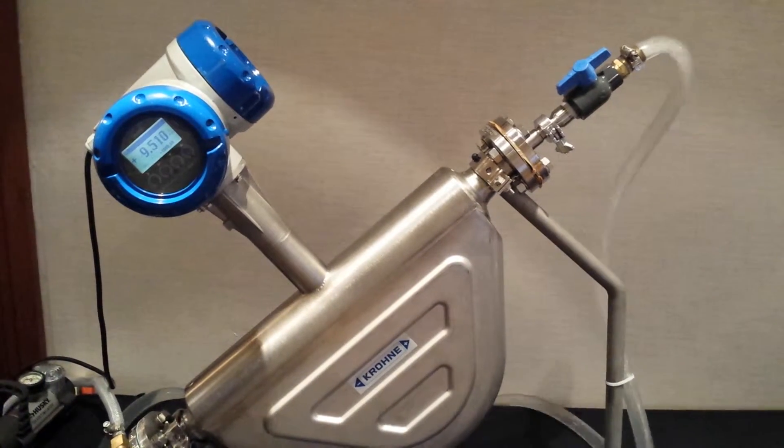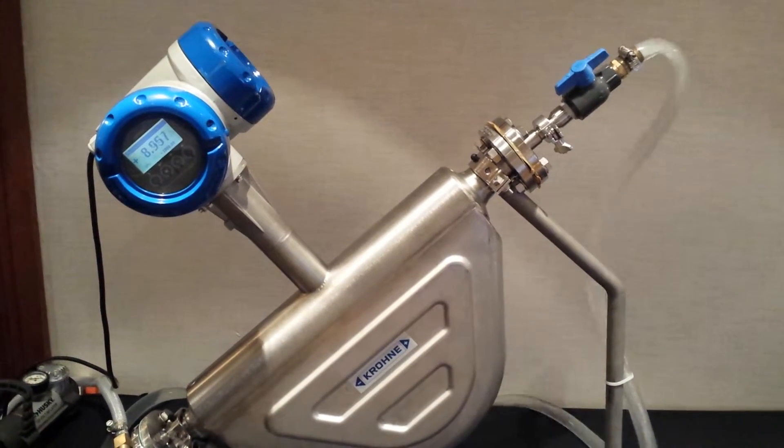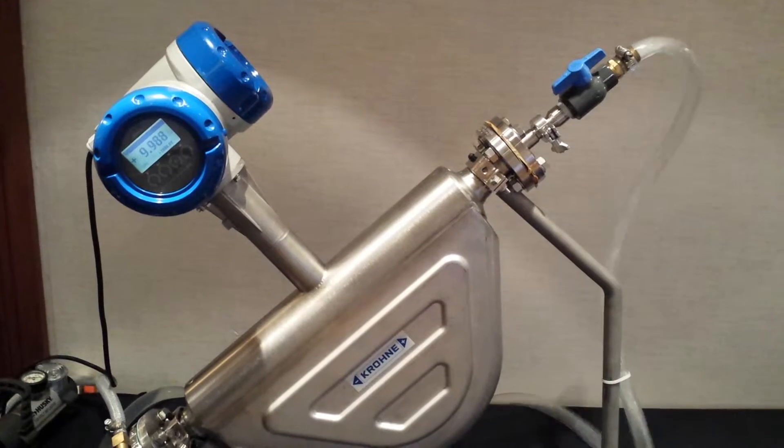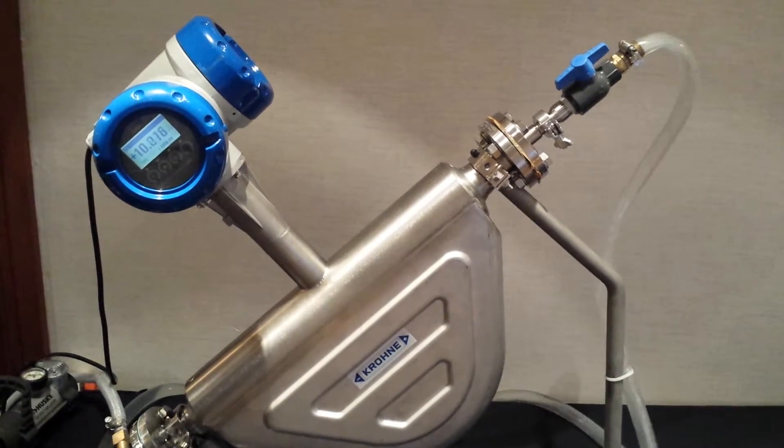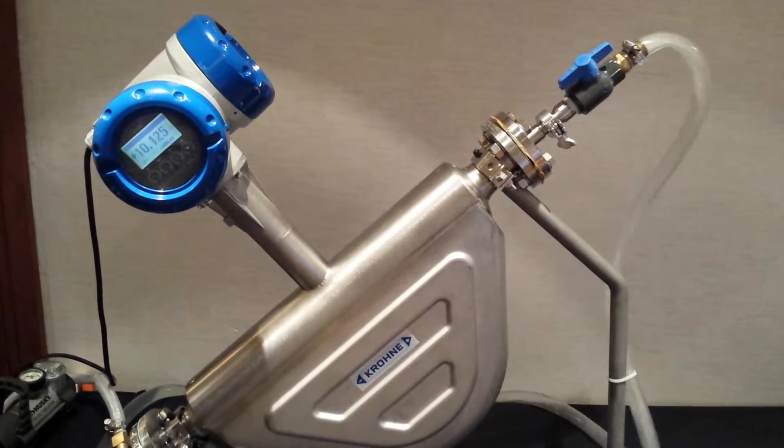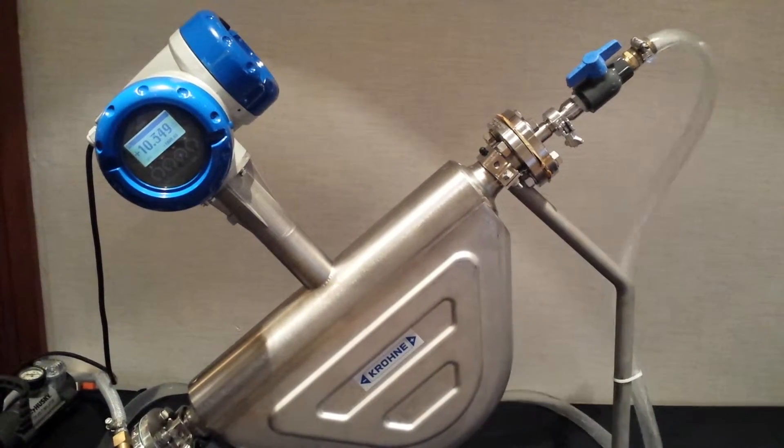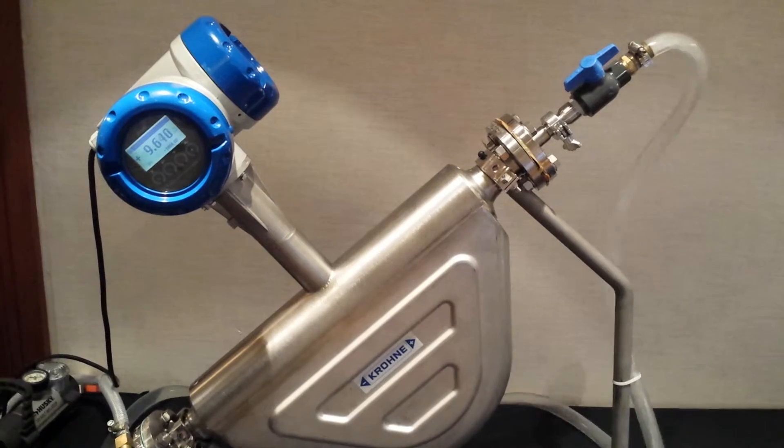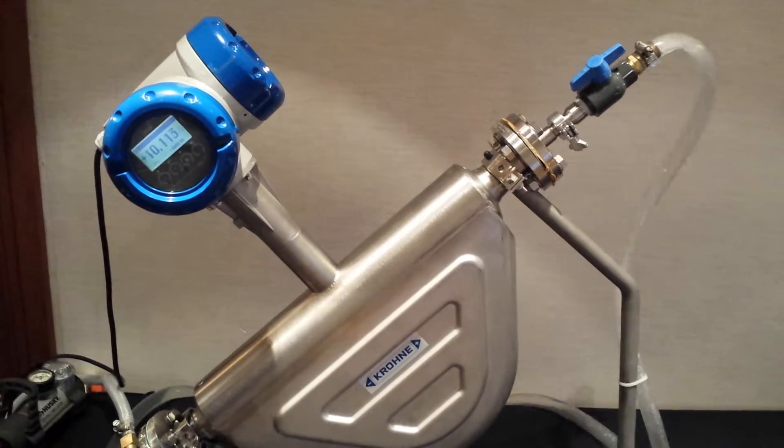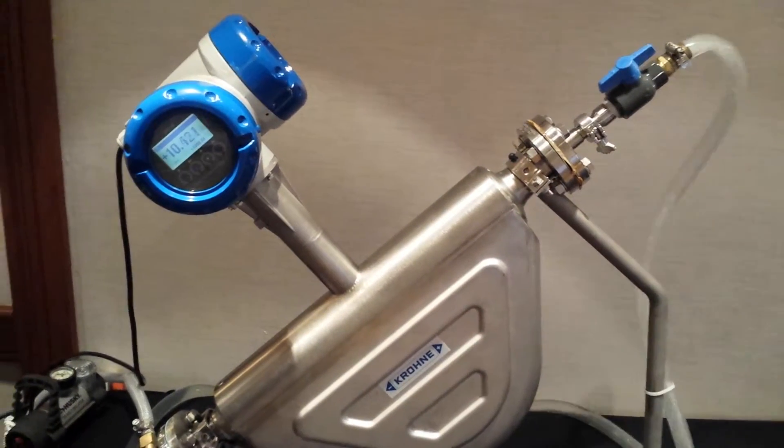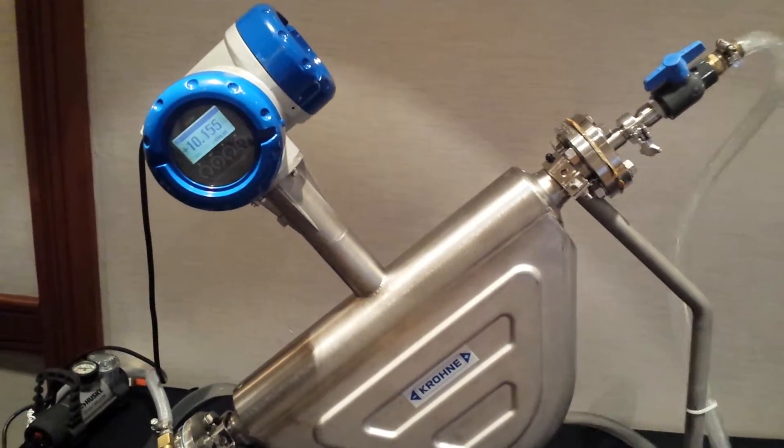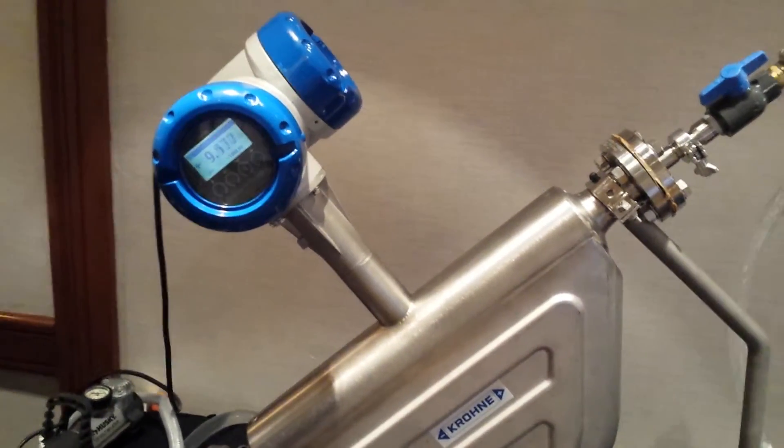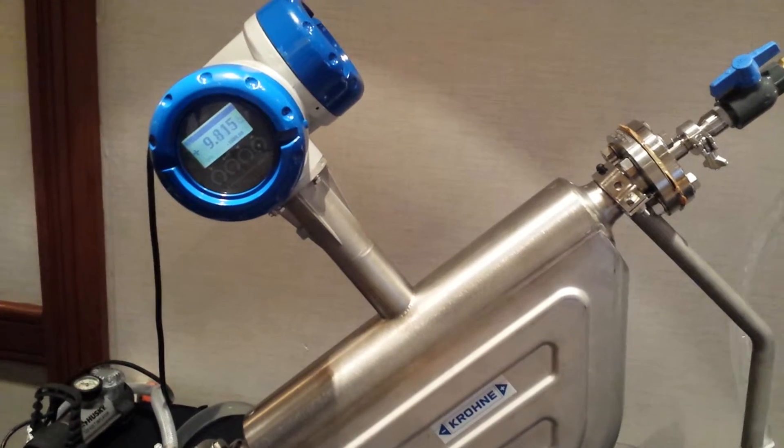Obviously the mass flow has dropped, which is what we want. We have more air, we have less water, so the mass flow has dropped. The two-phase indication has skyrocketed to over a thousand.